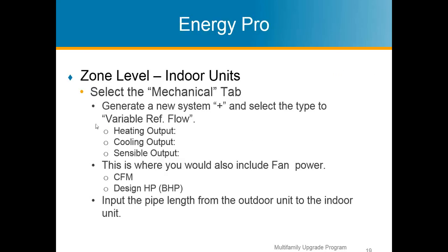Call it a VRF system, and you're going to be putting the heating, cooling, and sensible output of that system. So say it's the 1/2 ton to 1.5 ton indoor unit. You're putting in that system information and that's going to go into the residential apartment. So instead of putting your fan energy under the system level, you're putting your fan energy under this indoor unit zonal level. So the fan associated to that space, and that's where you're going to get your CFM. And then remember, we talked last time about the design horsepower, the brake horsepower.